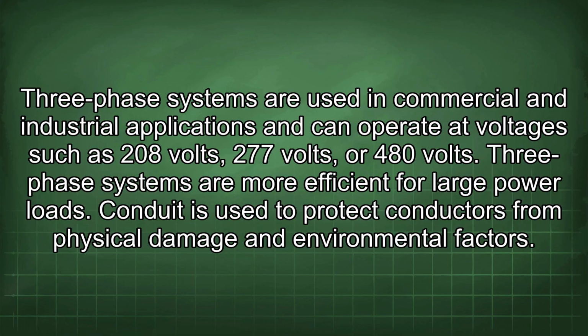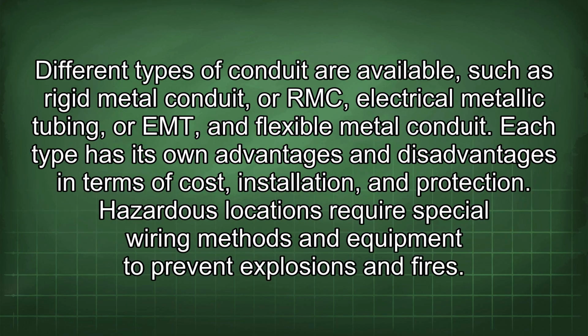Conduit is used to protect conductors from physical damage and environmental factors. Different types of conduit are available, such as rigid metal conduit, or RMC, electrical metallic tubing, or EMT, and flexible metal conduit. Each type has its own advantages and disadvantages in terms of cost, installation, and protection.